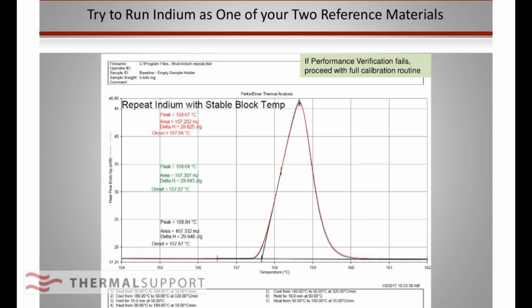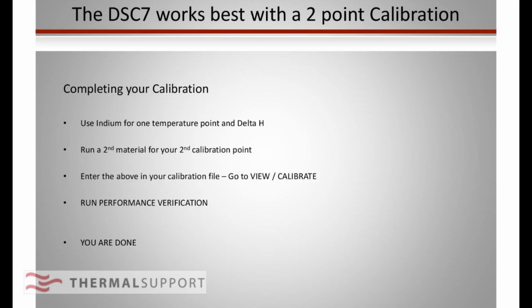If you can, try to run indium as one of your two reference materials. You can use it both for your delta H and as one of your two temperatures. If you can't, we understand. If you need help, give us a call. We'll see what we can do to help you out with that. But it works best with a 2-point calibration. If you try to stick with it, I think you're going to be happy. Use your indium for the 1 point, and delta H, the second material, for your second calibration point.